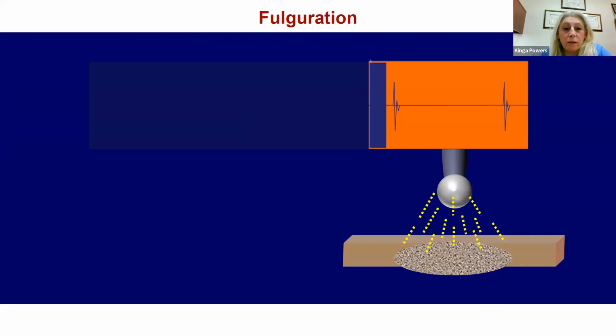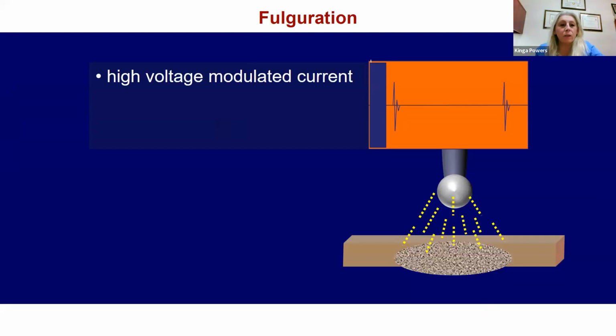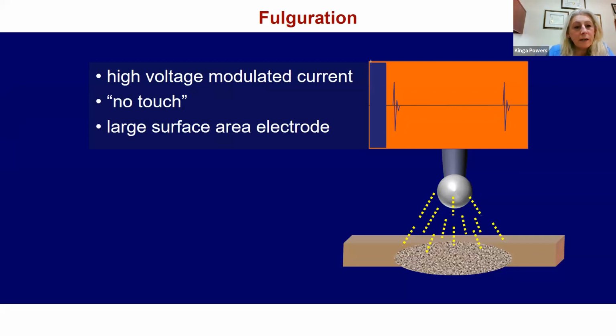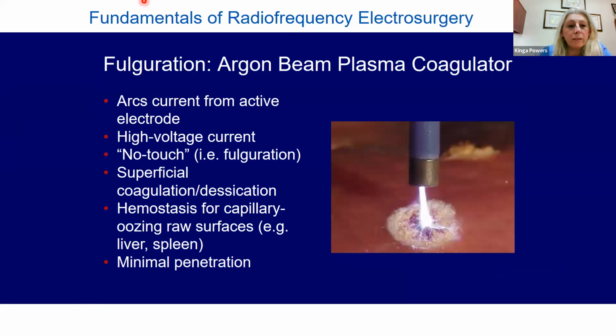This is used a lot with the argon beam, which uses fulguration in endoscopic surgery. It's a high voltage modulated current, no touch technique, with a large surface area of the electrode. An example is the argon beam plasma coagulator, a monopolar device. It uses argon gas to arc the current, which is sprayed onto the tissues and doesn't go very deep. Usually it's recommended to use 20 watts or lower on the coag setting, especially in endoscopy.